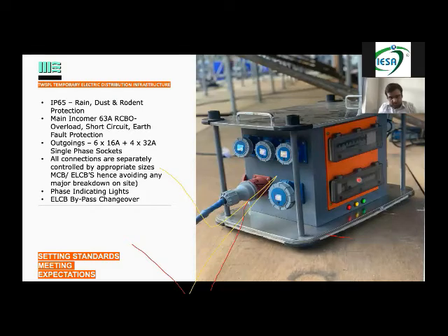So usually, according to the feedback, the show must go on, there should be no tripping. That is not dependent entirely on the power distribution company. It is dependent on the equipment which is being connected on it also. So during the show day, we do a small changeover. The supervision staff does a small changeover so that the show can go on without any trippings and all.